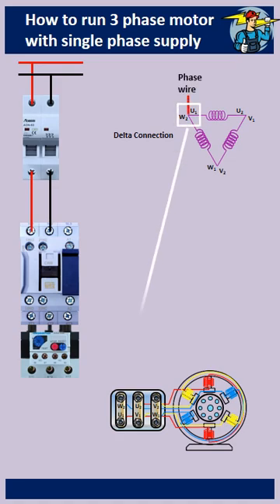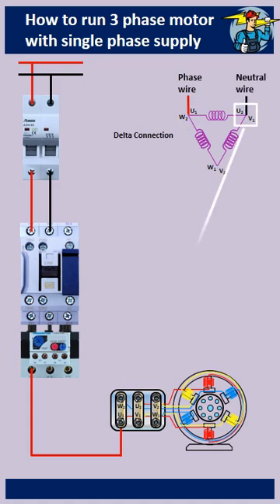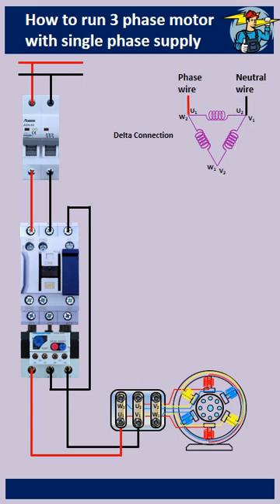Phase line need to be connected to U1 and W2 as shown in the diagram. Likewise, connect the neutral line to the V1 and U2 coil ends, as shown in the diagram.